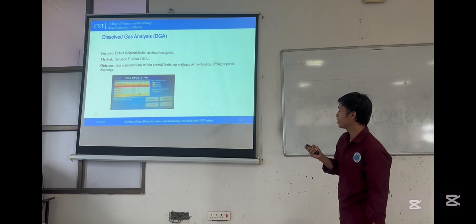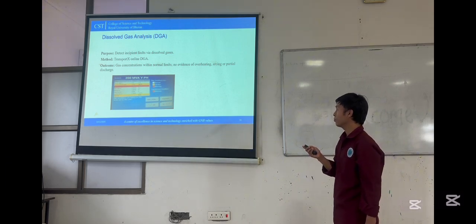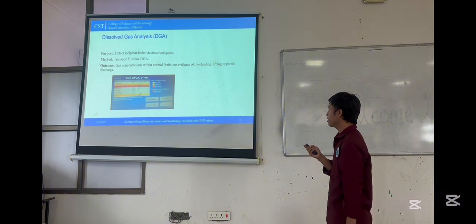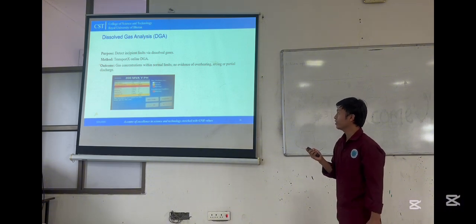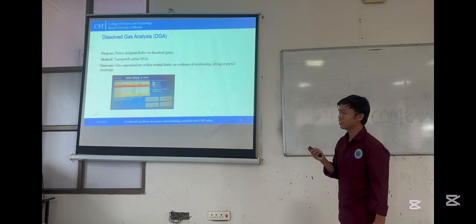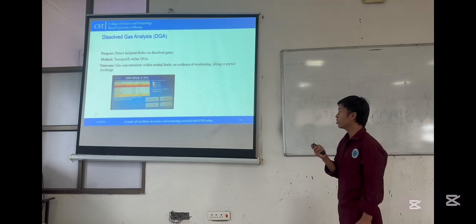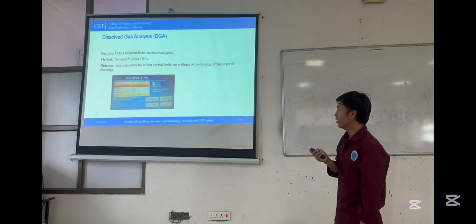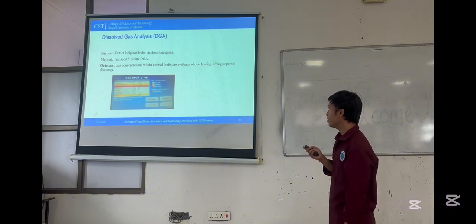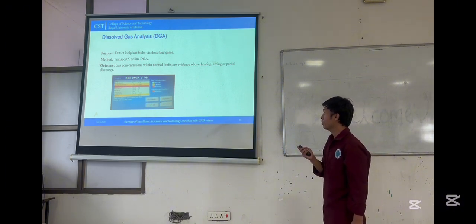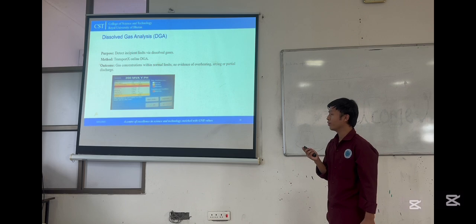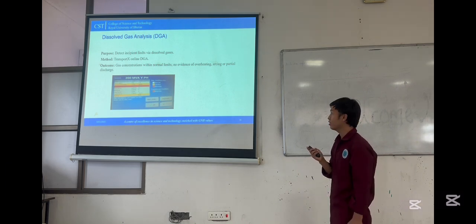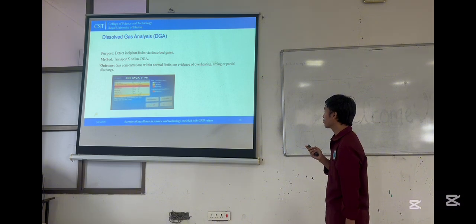And next is the dissolved gas analysis, and the purpose is to detect incipient faults by the dissolved gases in the transformer. This is mainly to detect the internal faults in the transformer. In this dissolved gas analysis, we have used the Transport X instrument to detect.